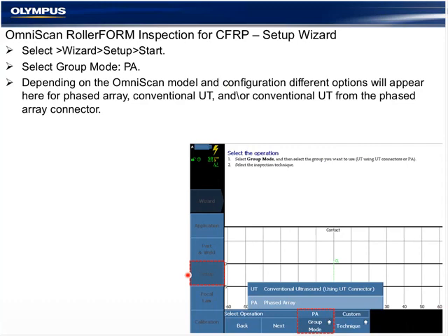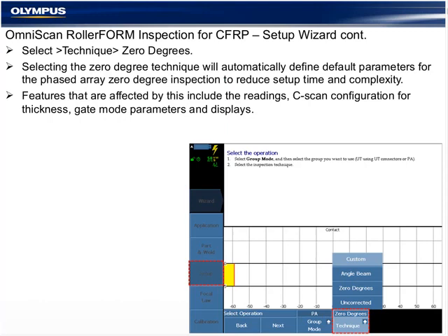In the setup wizard, on your first step, you're going to see a group mode, and depending on the instrument model, either an OmniScan MX2 or SX, and the pulser configuration, there could be several options here. The RollerFORM wheel probe is a phased array inspection only. Select phased array. And for the technique, we're going to select 0 degree. The three available techniques that we see here set defaults for the displays, the gate modes, and the color palettes, and they will shortcut our setup a little bit and put the OmniScan in a condition most favorable for this application.